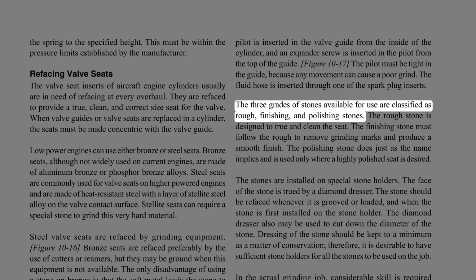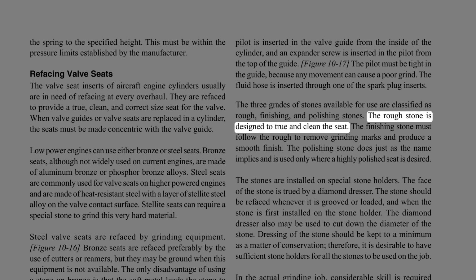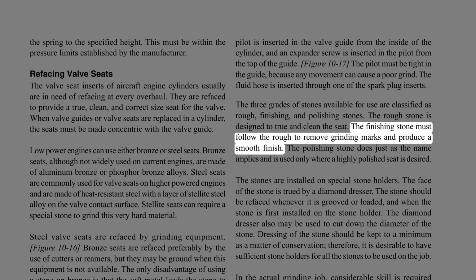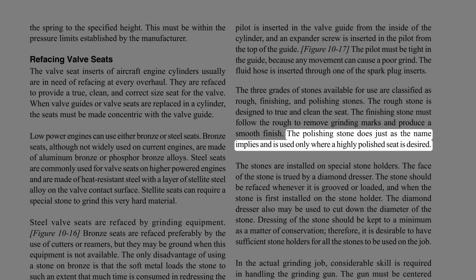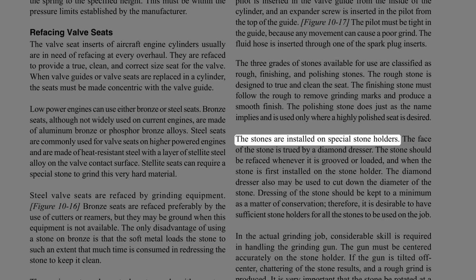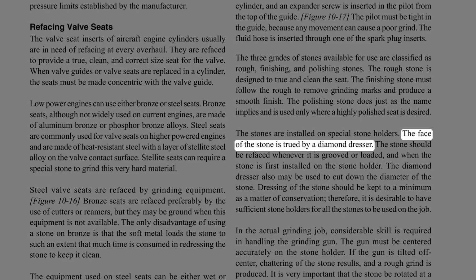The three grades of stones available for use are classified as rough, finishing, and polishing stones. The rough stone is designed to true and clean the seat. The finishing stone must follow the rough to remove grinding marks and produce a smooth finish. The polishing stone does just as the name implies and is used only where a highly polished seat is desired. The stones are installed on special stone holders. The face of the stone is trued by a diamond dresser.